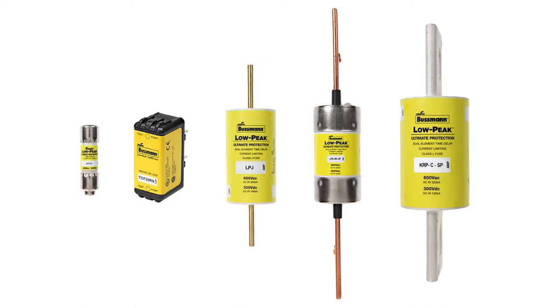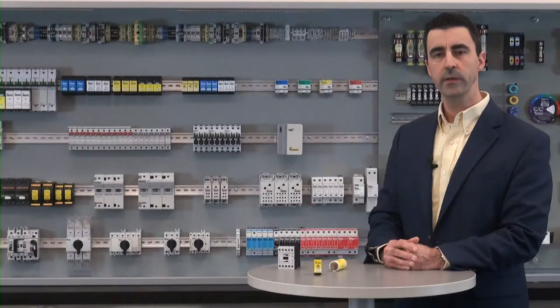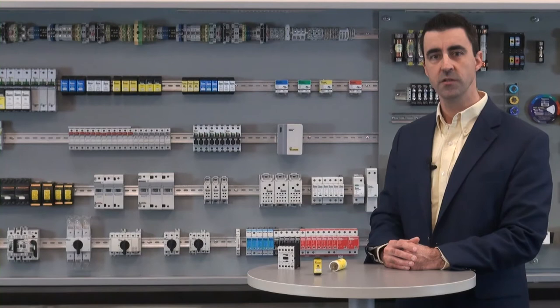Providing and specifying equipment with short circuit current ratings equal to or greater than the available fault current will not only comply with the National Electrical Code, but will help provide a safer, more reliable electrical installation. Current limiting fuses can help achieve these higher ratings due to their current limiting characteristics.